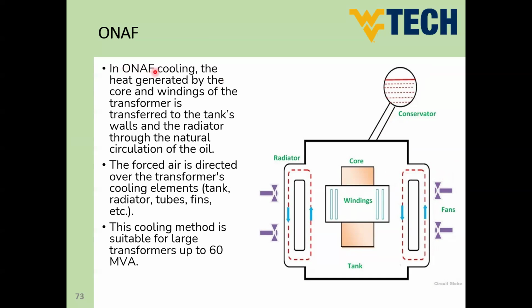In oil natural air forced cooling, the heat generated by the core and windings of the transformer is transferred to the tank's walls and the radiators through the natural circulation of the oil. Until this point, it's the same as the oil natural air natural. But the forced air is directed over the transformer's cooling elements, the tank radiator tubes. This cooling method is suitable for large transformers up to 60 megavolt ampere. So we can say from 15 or higher to 60 megavolt ampere, we can use this type of cooling, oil natural air forced.